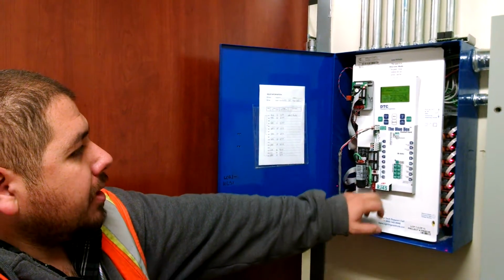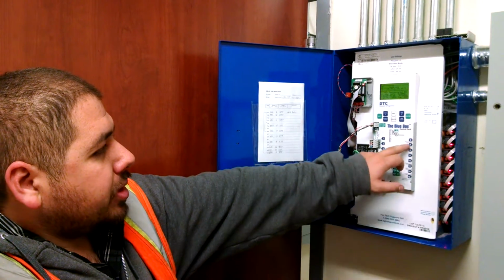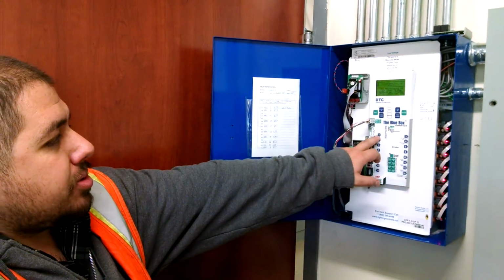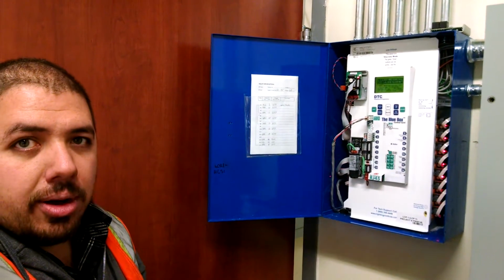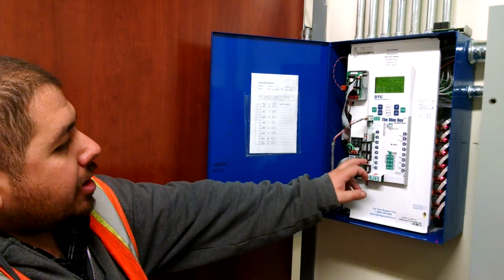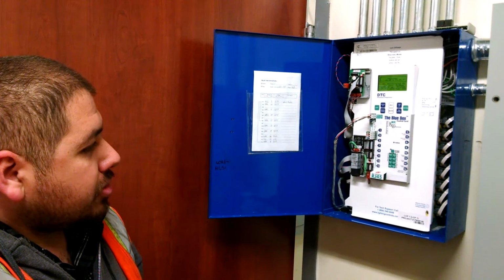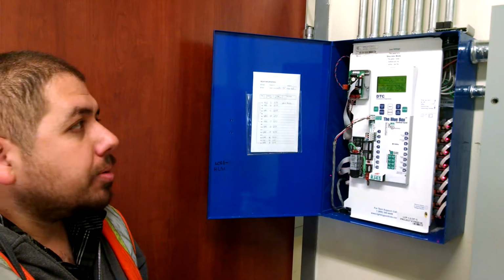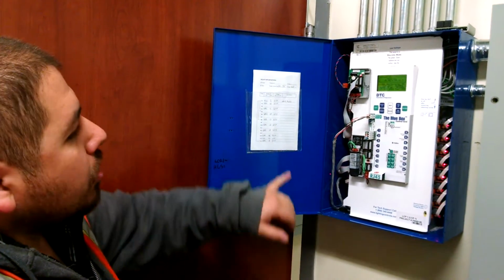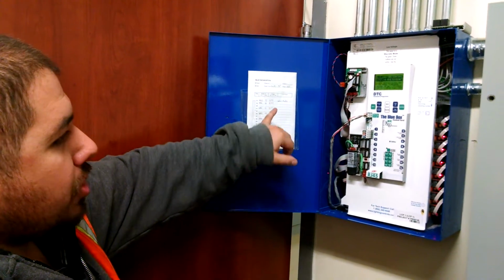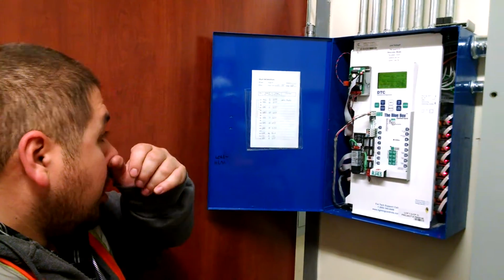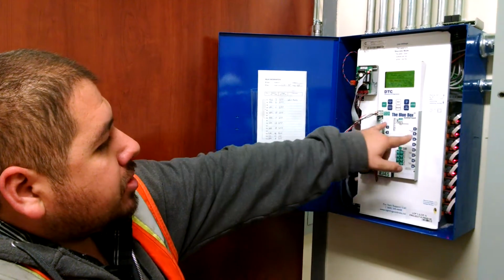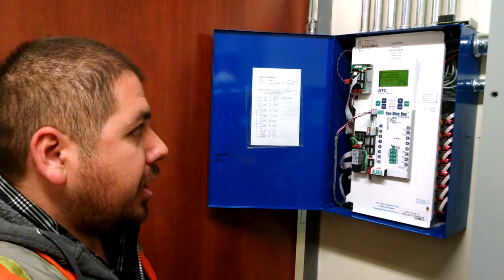Okay. Each one of these little buttons here is a relay control. If I push that button, you heard the relay click. Little light turns on, relay off. You have a hand-auto switch. Hand turns all relays on. Auto puts it back into programming mode. Of course, there's a panel schedule on the side here, so you guys know what is on each relay. And finally, this photocell right now is programmed to control all relays in the panel.